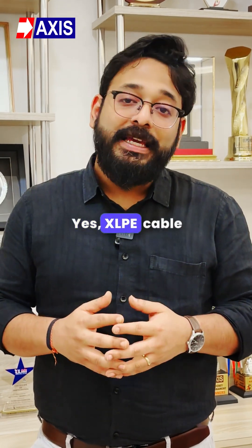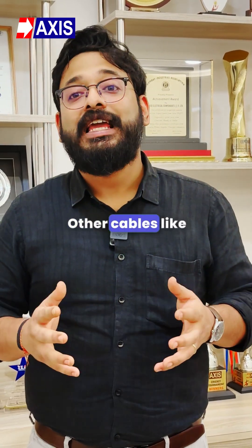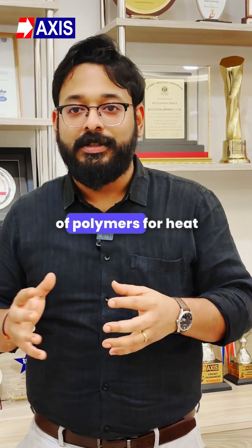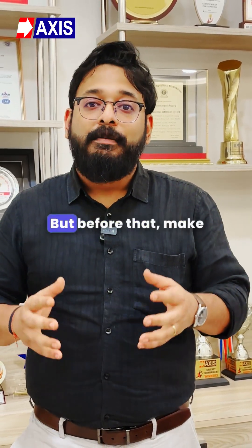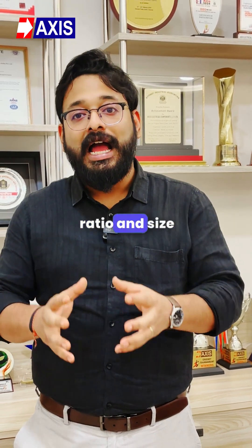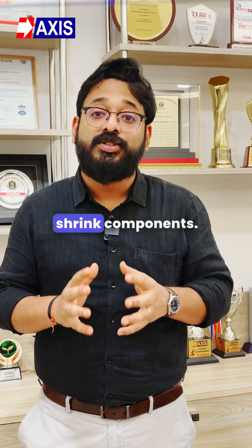XLPE cable works well with polyolefin heat shrink products. Other cables like PILC and all need different grades of polymers for heat shrink products. But before that, make sure that the shrink ratio and size fit is properly measured before you choose any heat shrink components.